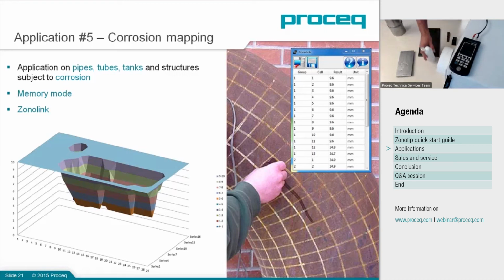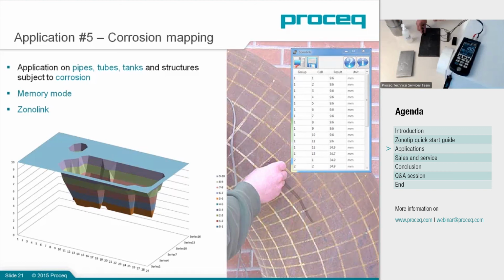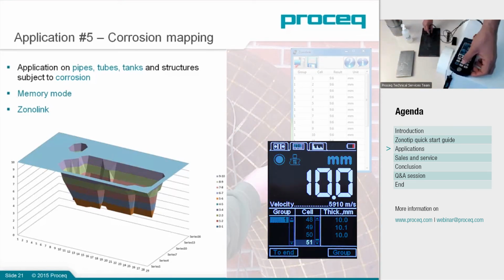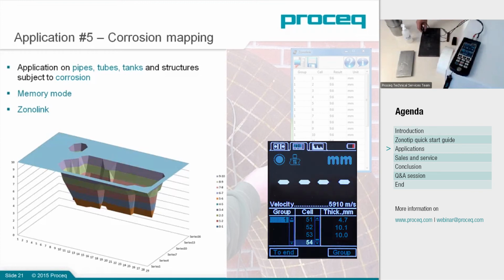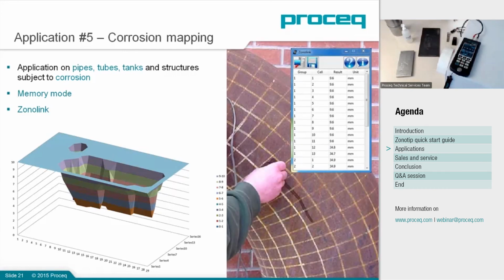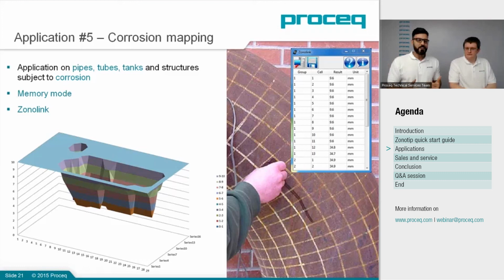So if you define, let's say, a grid size on this, and put the device into the memory mode, we're going to start testing from the side. And as we do the measurement, we're going to store along our grid every single measurement that we do. As you can see, as I'm moving along, the thickness is changing. So again, I'm going to move ahead, carry on doing the test on this grid, and you can see how the thickness readings are changing along my sample. We will obviously carry on doing the test for the entire sample. When the testing is done, we'll take our Zonotip device back, let's say, to our office. Extracting the data would allow us to then plot a graph.